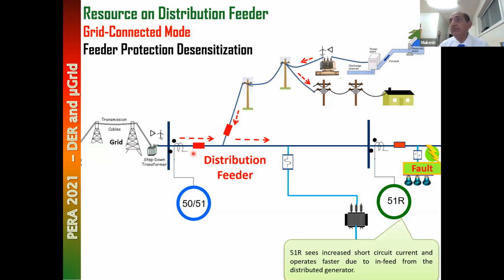Good. So this protection sees a higher short circuit level, and so the protection will operate faster. We want this protection to operate faster than that. That's the inverse time protection coordination. In the inverse time protection coordination, you want this protection to operate faster than this. So this distributed resource is helping this protection to operate faster. We are happy about it.